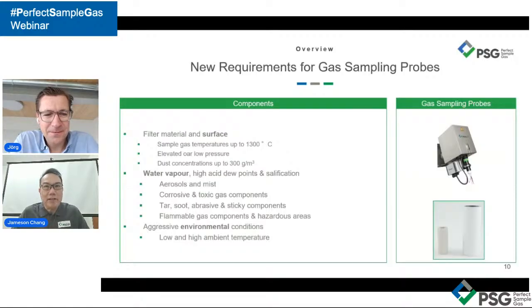So therefore, it is very critical that in the sample probe design, our PSG sample probe has taken into consideration a few factors. Factor number one is safety. Factor number two is a prolonged maintenance interval. Factor number three, you don't have to rely on tools to replace the filter element. Factor number four, which is the most critical one, which many people don't believe, is that once our probe is put up in the stack, based on emission monitoring generally being less than 100 milligram per meter cube, our probes stay up there without a back purge. Even though you do need a back purge, you do not need attention after 1 year just to replace the filter as part of the maintenance. I think that's a great advantage of this technology.